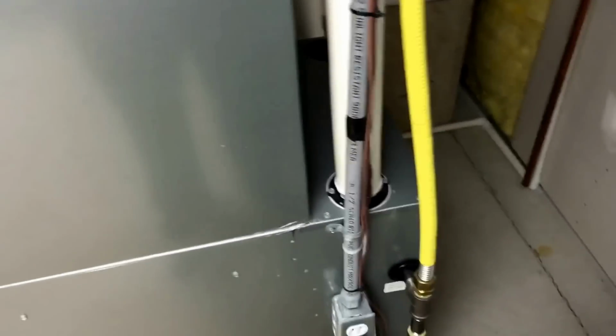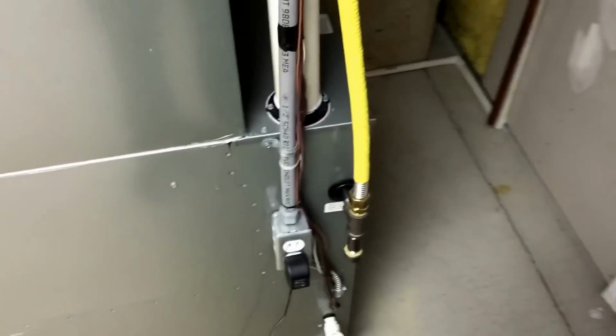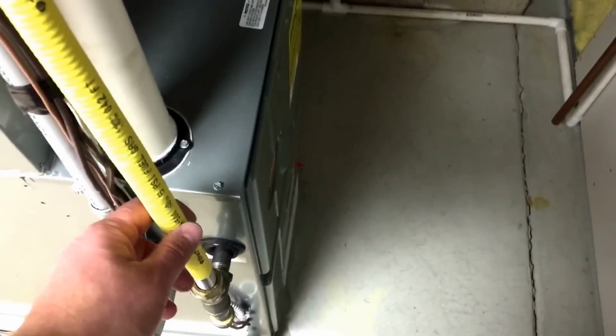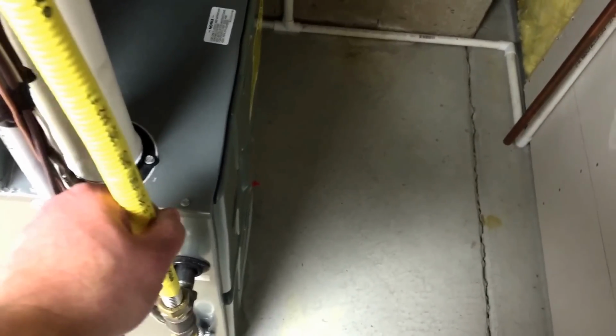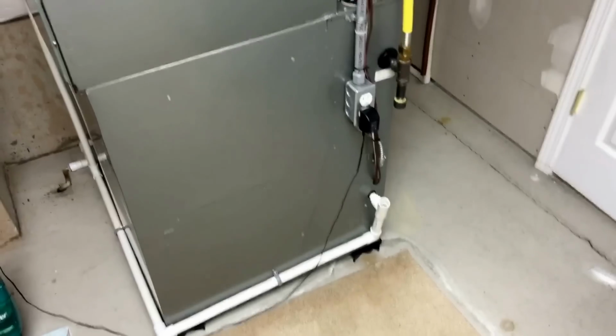And it was just lazy. No drip leg on the gas line. And the problem was actually a gas pressure issue. The way that they had piped the gas line, I couldn't even get my equipment on to test the incoming gas pressure into the valve, because they had incorrect piping, because they had to drill a hole through the side of the unit.